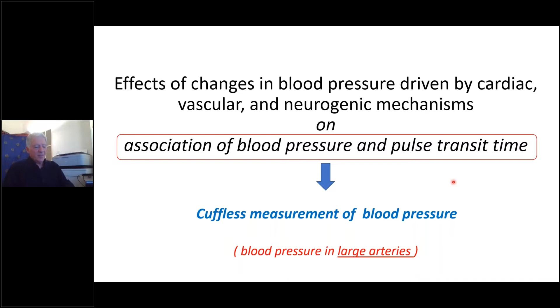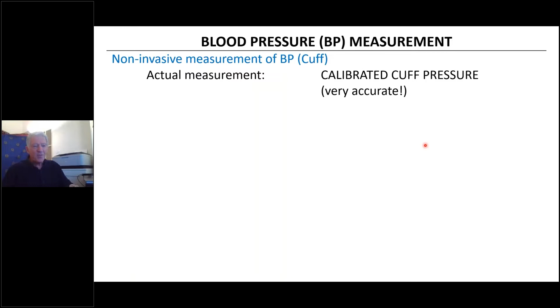So let's recap a little bit what we know about blood pressure measurement. Now in the cuff, using the cuff sphygmomanometer, the actual measurement that we do is a pressure measurement in the cuff. So it's a calibrated cuff measurement. Calibrated if we use a transducer, and if we use a column of mercury, one doesn't need calibration. We trust gravity. This is very accurate. It's not true that the measurement of brachial blood pressure is not accurate. It is probably the most accurate measurement we have in medicine. That measurement, the measurement of cuff pressure. What is relevant is that the association of that cuff pressure with arterial pressure occurs through secondary phenomena. And these are usually either blood flow or wall vibrations related to Korotkoff sounds.